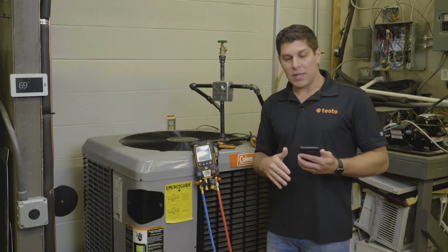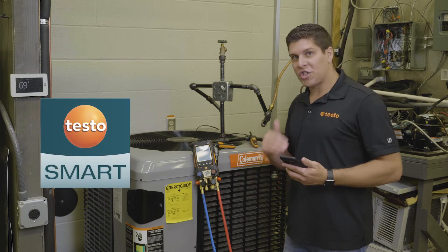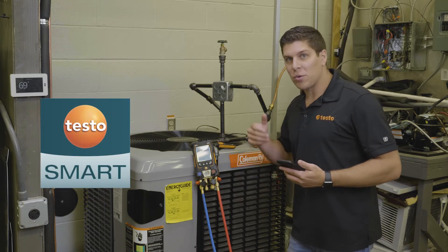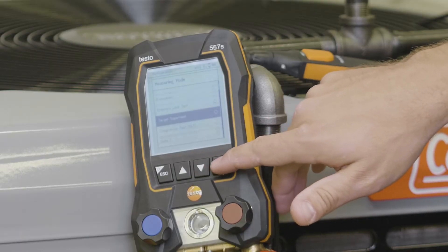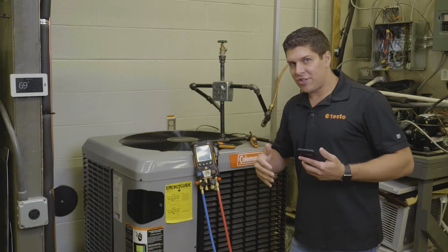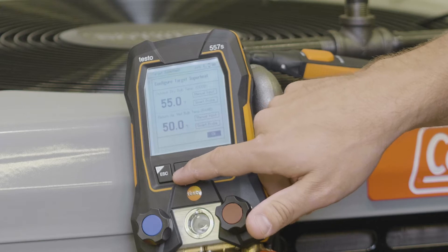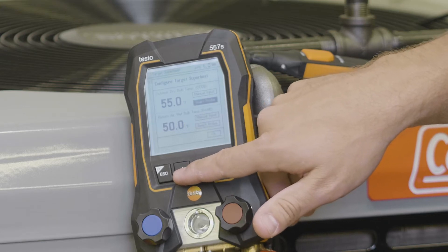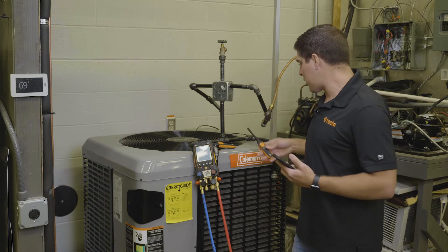I want to make the point that the manifold is controlling the app at this point. So if you want to change your measurements, very simple — do it on your manifold and you're set to go. We're going to scroll down to target superheat. One of the nice features is we can do a simple configuration up front. We'll go into our outdoor dry bulb — I have two of my 605i thermohygrometers from Testo.